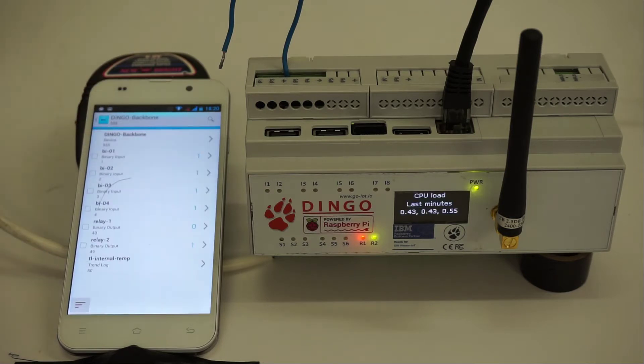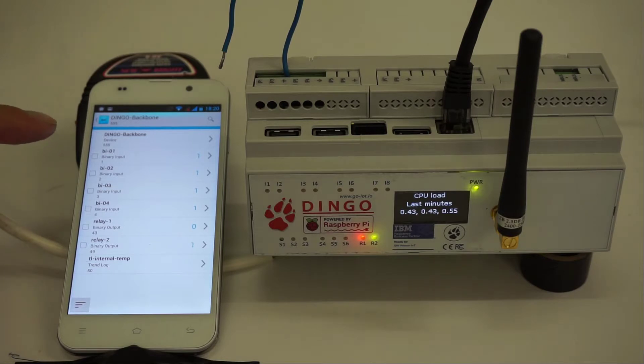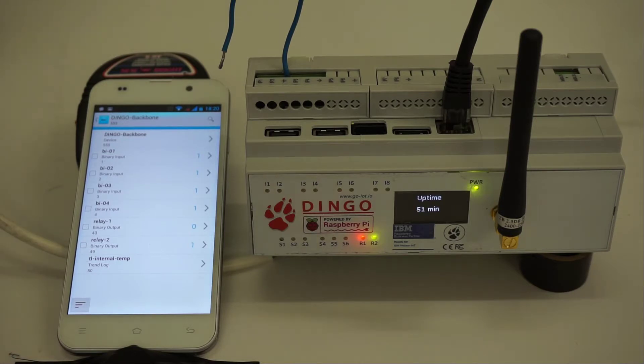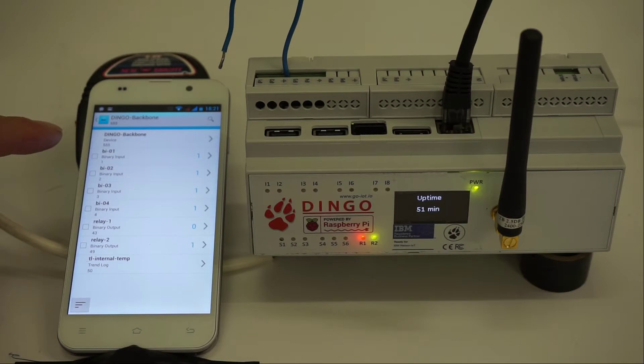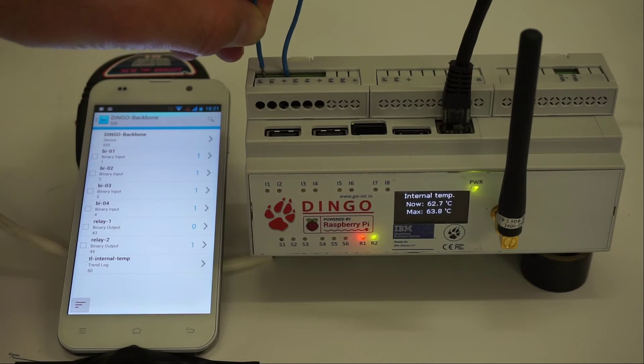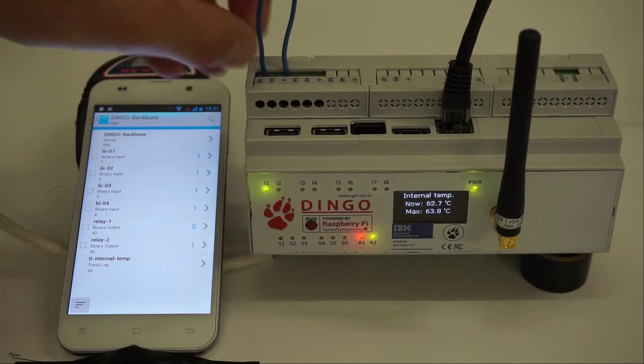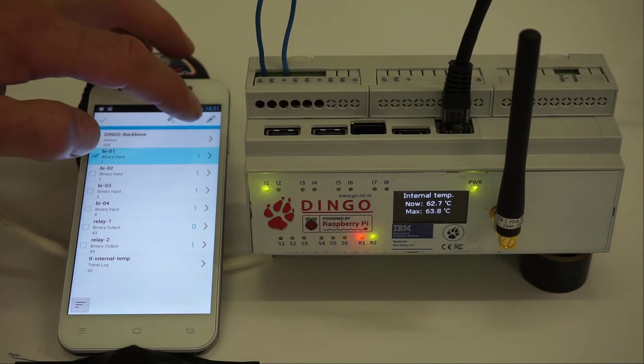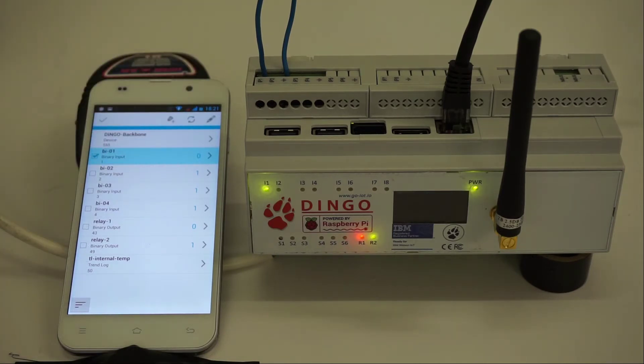Let's select that device. We can see all the BACnet objects — it's very simple: there are four binary inputs, two relays, and a trend log (which is probably not useful to explore right now). Let's see how this works — if I short binary input number one now, it's shorted. Let's poll it again and read it — we see it reads zero, so that's working fine.